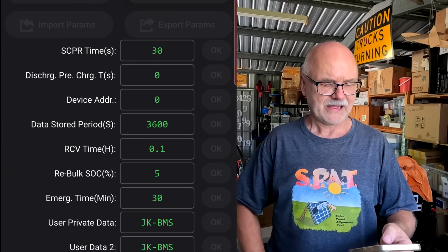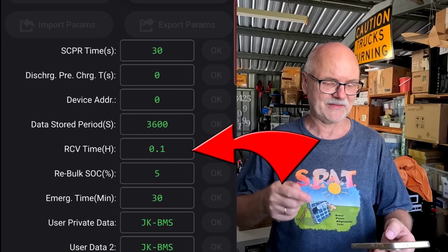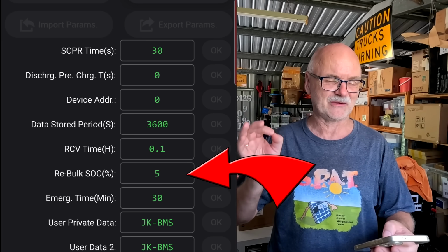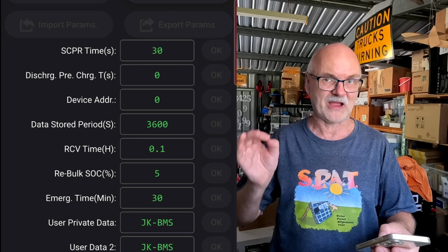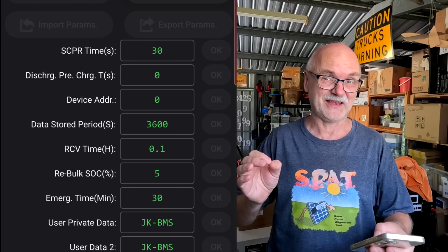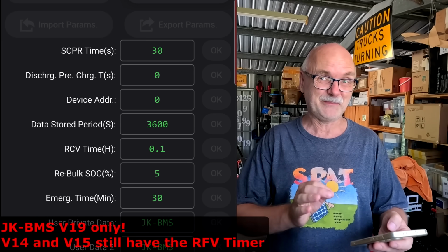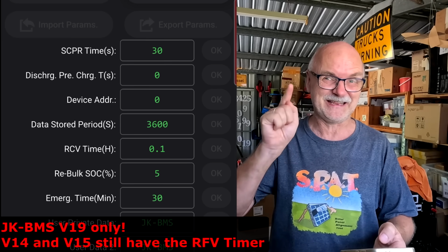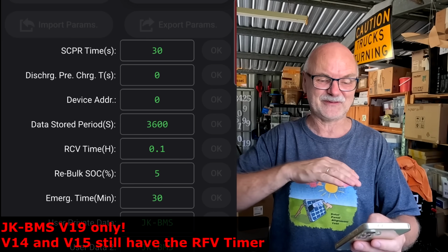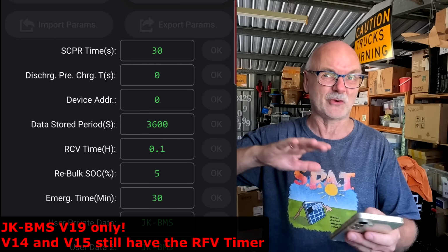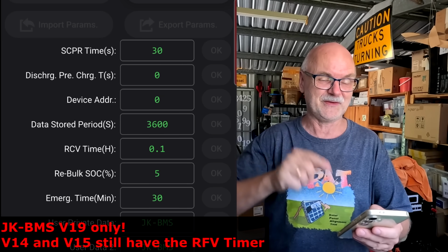Here it is: RCV timer 0.1 hours, and then there is a rebulk state of charge percent of 5% set. This is the default setting for this parameter, but it only appears if your BMS is sitting on master. The slave does not control your charging, it does not communicate to your inverter, only the master does.